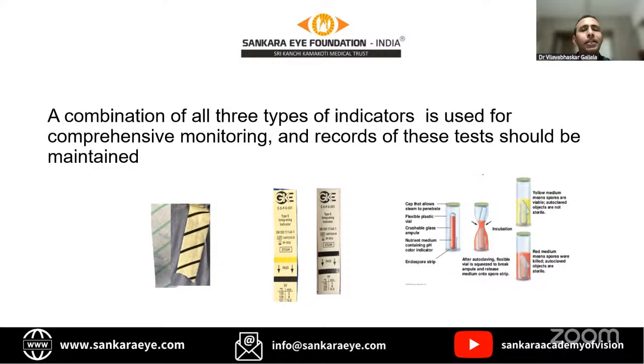And most importantly, you should record all the test results and maintain those records, not only for medico-legal purposes. If you receive any loads without a recorded sterilization, you can go back and check, and re-verify the process to see how it happened again.